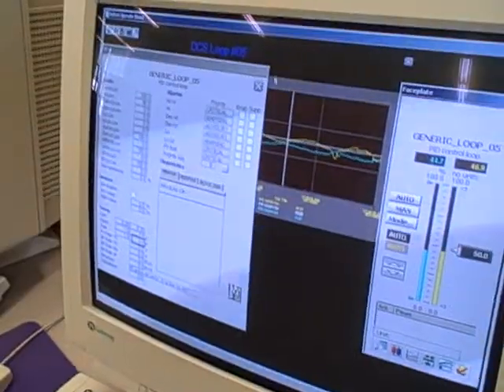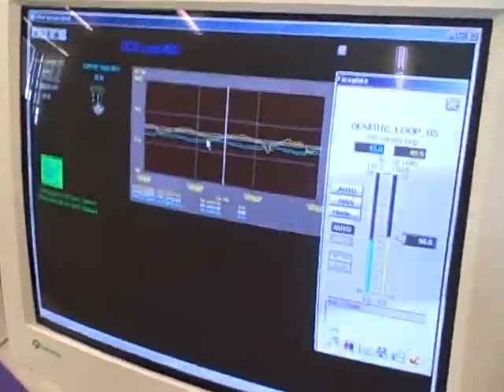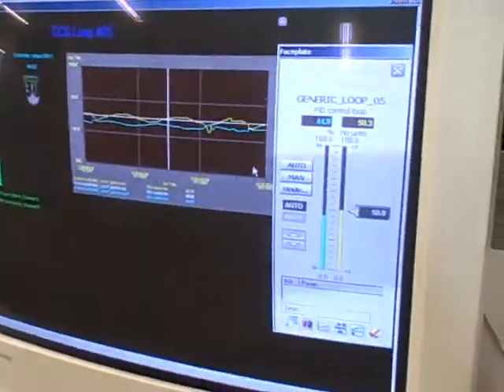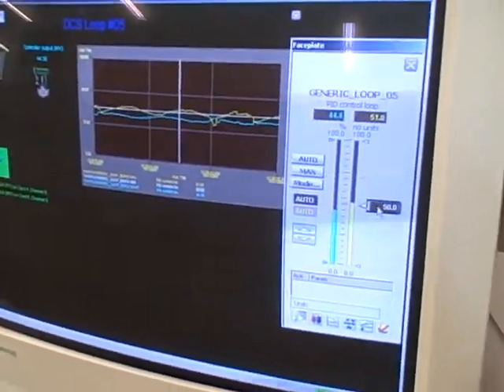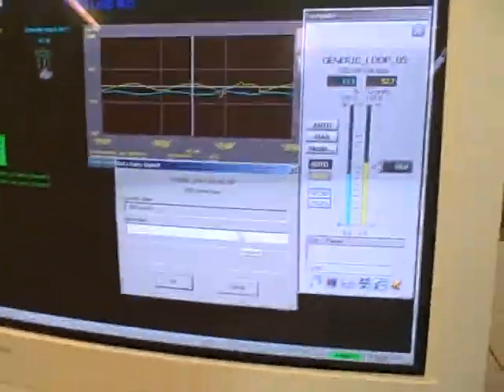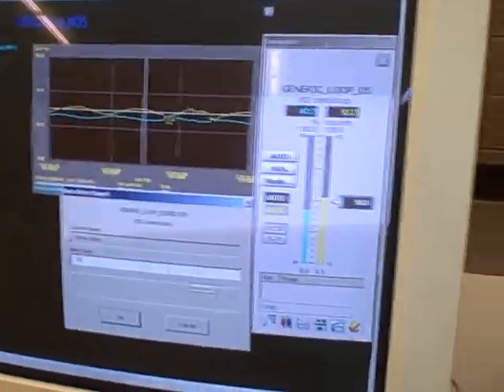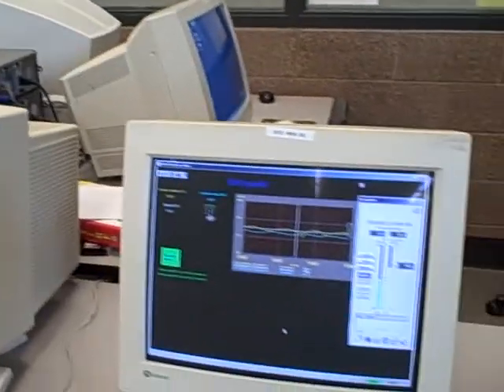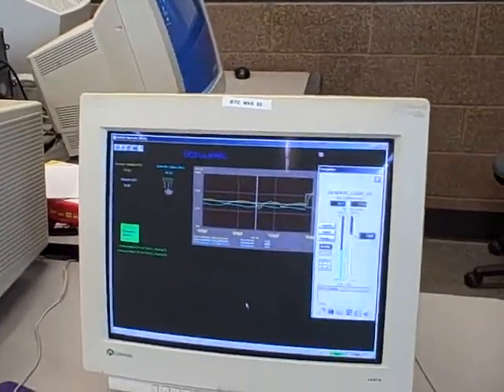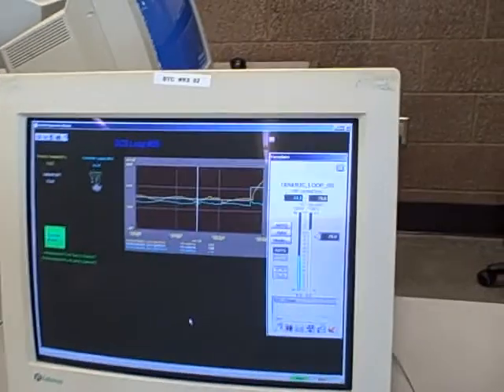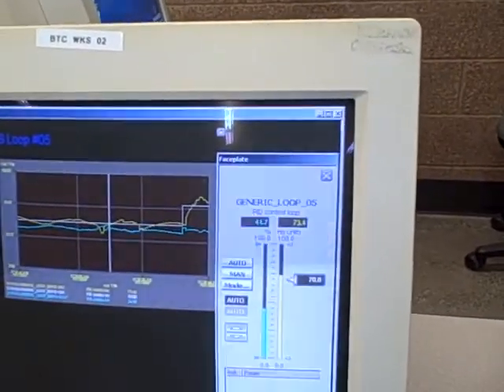So with the Delta-V system, we have our tuning screen, which I'll close down here. We've got our trend loop, and then over here our controller faceplate. I can call for a different setpoint. In this case, I'll go to 70% instead of 50% speed. When I do that, it calls for a higher speed. You can hear the turbo wind up in speed, and you can see this settle at the new setpoint.